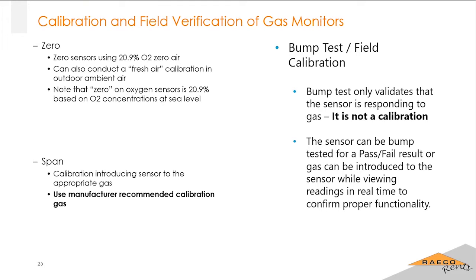And for the RAE products, that sheet that I had up earlier with the cross sensitivity is basically a spec sheet of every sensor, and it will show the recommended calibration gas to use as well. So the span is making sure that 100 parts per million is 100 parts per million on the instrument, for example. And again, the bump test, important to know, is not a calibration. It's just validating the response of the sensor, so you're just going to get a pass or a fail on that. It's not going to adjust the readings of the sensor in any way. Only your zero and span calibrations will do that.